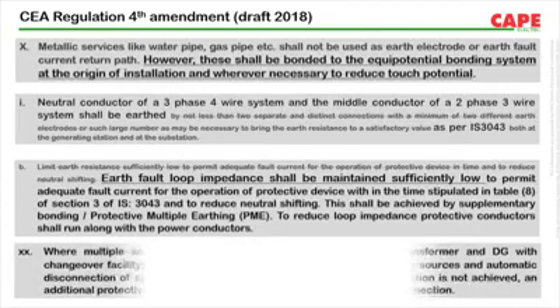Another improvement made in the 4th amendment draft is that the neutral conductor, the neutral of a transformer or a DG, shall be earthed as per IS 3043. Now, instead of earth resistance, you should maintain fault loop impedance. You should maintain a very low fault loop impedance so that the supply is disconnected during a fault within the time explained in IS 3043.